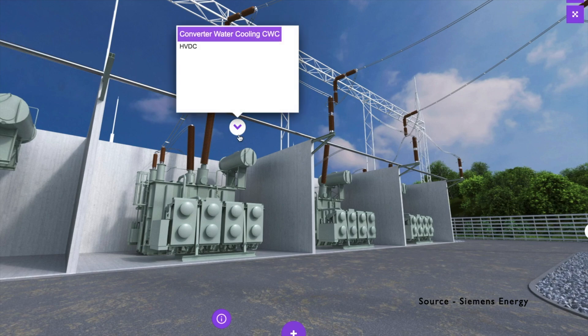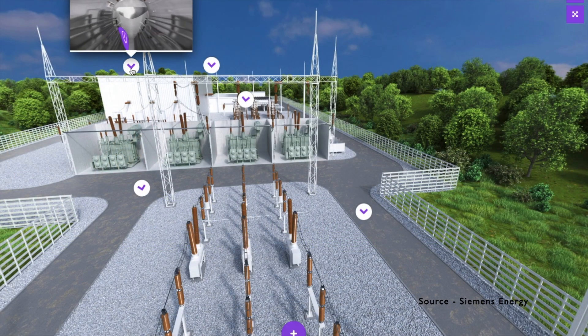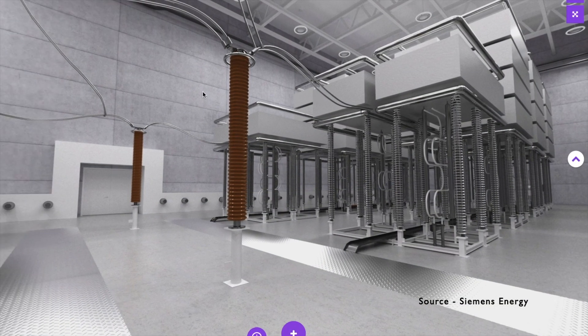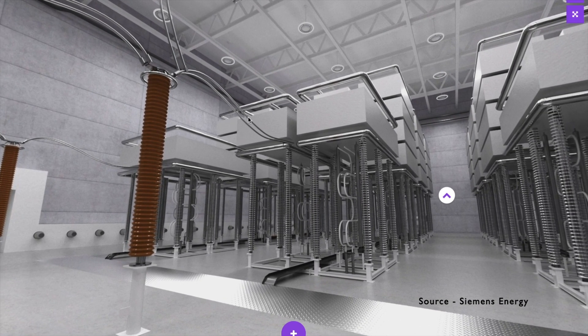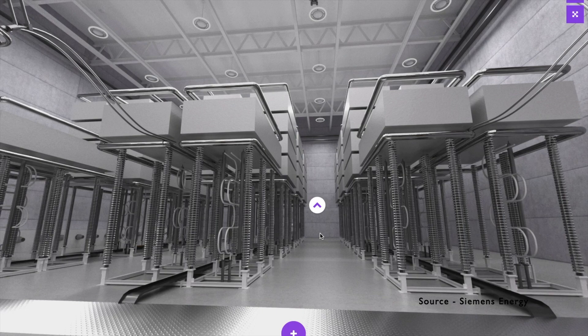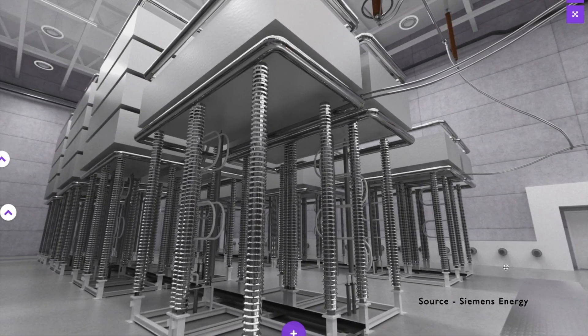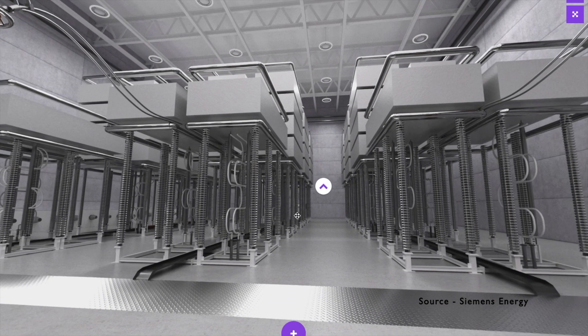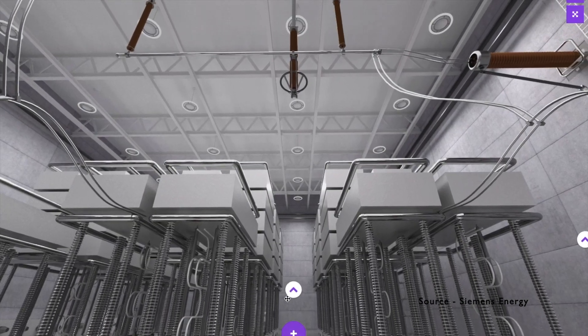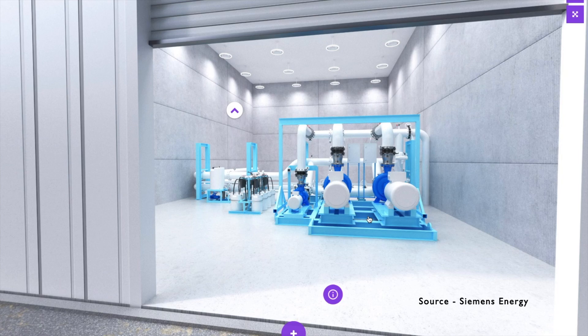Now let us go to the converting station. Inside the converting station, you can see we have lightning arrestors installed, and the supply is given to the converter using thyristor technology — this is where AC will be converted into DC supply. Some technologies can also do it in reverse, converting DC into AC as well. During operation, this gets heated up — a lot of heat is produced. So to cool that, we also have a dedicated cooling station, which helps in cooling down the converting station.